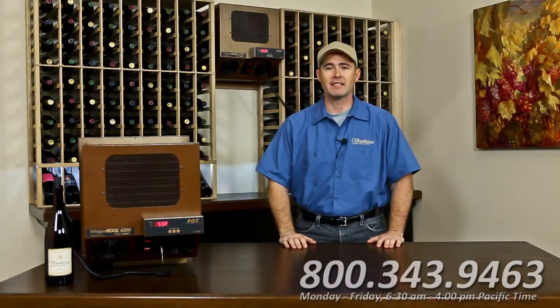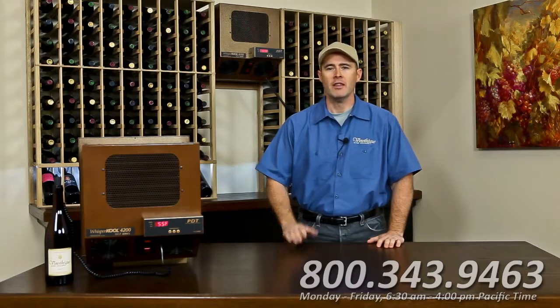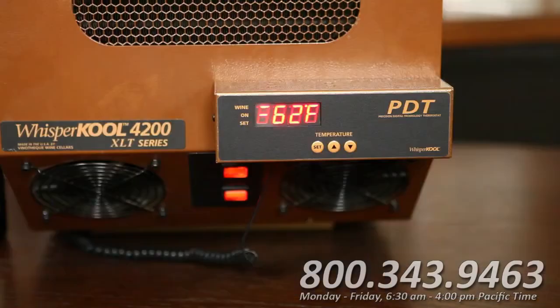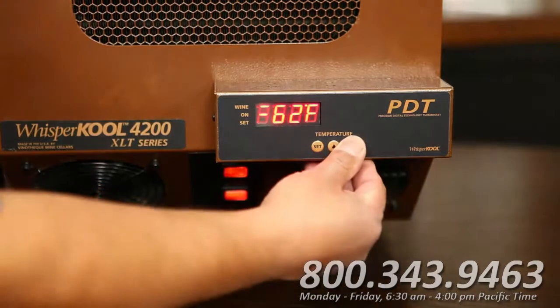Next, you should run the bypass test that we just showed. Also, there's another way to test your thermostat. Press and hold the down arrow while the unit is running. You should see a 90-minute countdown on the display.